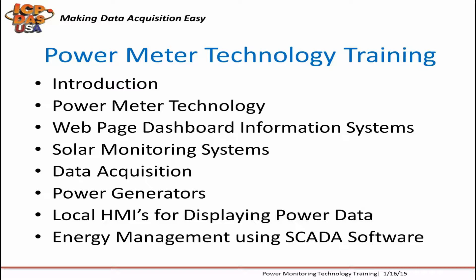We have a wide selection of power meters that communicate over various protocols, including Modbus RTU, Modbus TCP, and CAN protocols. Our Modbus RTU units can communicate up to 4,000 feet without a repeater. Our Modbus TCP units can communicate over 300 feet without an Ethernet switch. Our CAN units can communicate over 100 feet without a repeater.